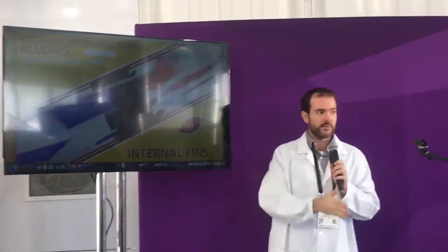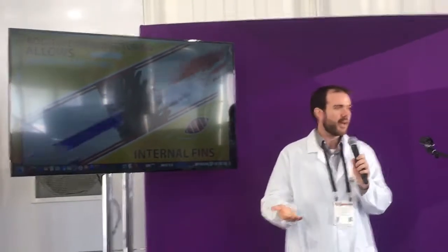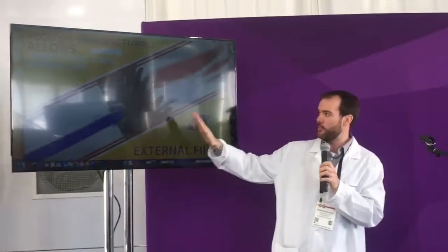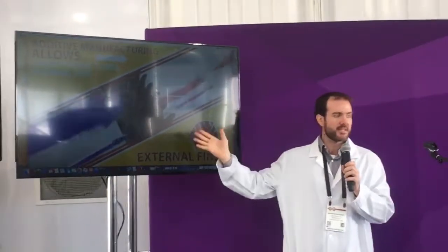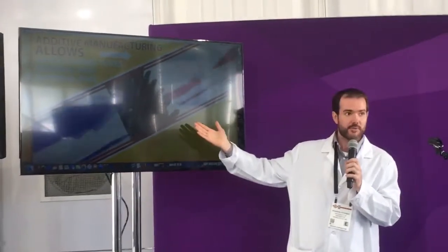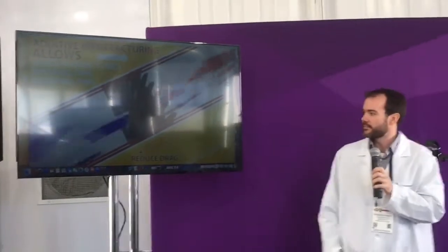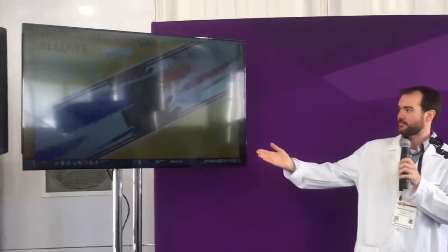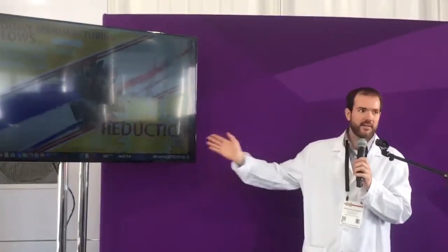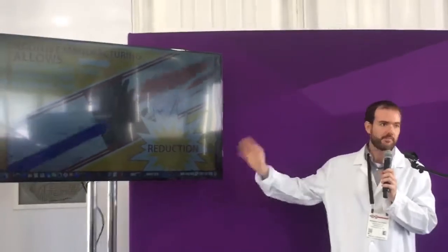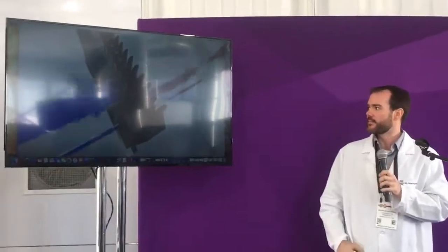We're able to produce those uniquely shaped tubes with those internal offset strip fins because we're using an additive manufacturing process. In a single printing operation that goes in the tube direction, we're able to crank out a device that's ready to operate with low pressure drop, lower than circular tubes would provide, and maximized heat transfer on the oil side. So there we see, with these uniquely shaped tubes, we maximize airflow and, again, maximize heat transfer, which is the main goal of this system.